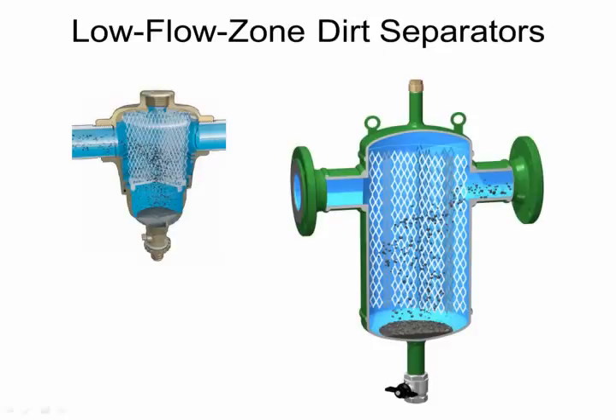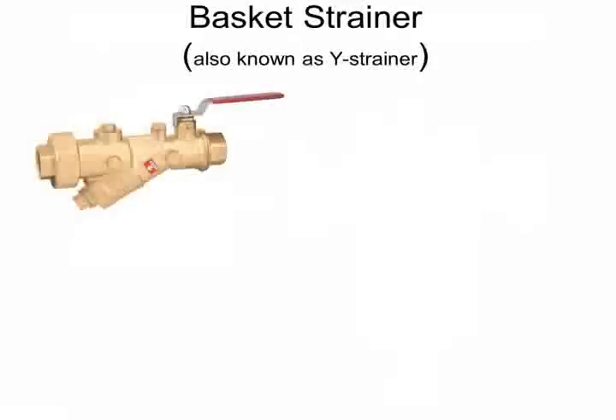So how do these low flow zone separators work? Well, here's a small one, a residential one. Here's more of a commercial. As fluid comes in laden with debris into a separator, the velocity slows down dramatically. And these meshes are designed to deflect the debris out of the path of the flow. As a result, you end up separating the debris away from the water, not filtering it, but actually separating it away from the flow path. And as a result, you don't get any pressure buildup as it does its thing, as opposed to, say, a Y filter or a basket cartridge filter.